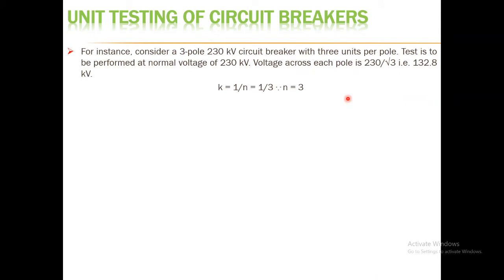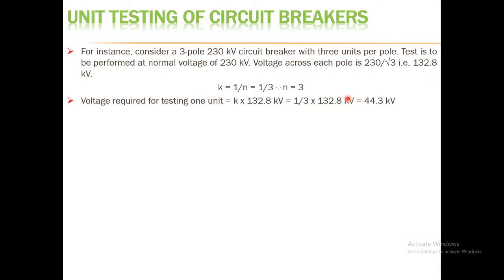We know that the voltage to be applied must be reduced by a factor K. K equals 1/N = 1/3, since N equals 3. So the voltage required for testing one unit is K × 132.8 kV, which is one-third of 132.8 kV, giving 44.3 kV. This is the voltage needed to apply to one pole of the circuit breaker during the unit test.